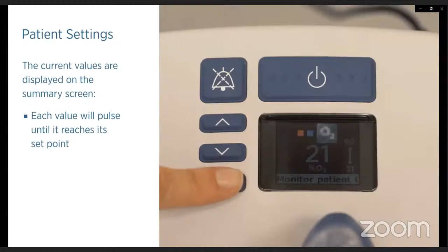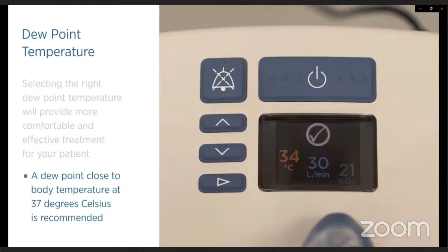Selecting the right dew point temperature will provide more comfortable and effective treatment for your patient. A dew point close to body temperature at 37 degrees Celsius is recommended, though you may like to reduce the dew point temperature if the patient complains that the gas temperature is too warm.